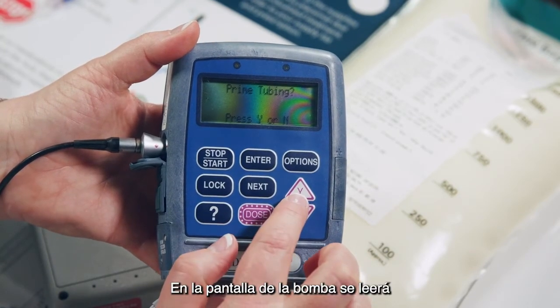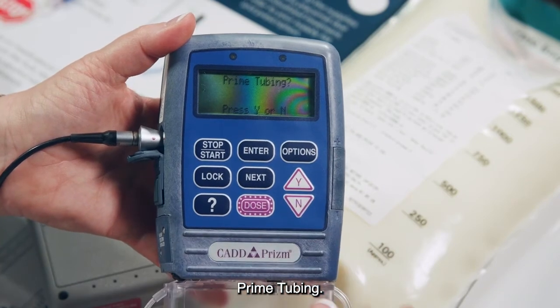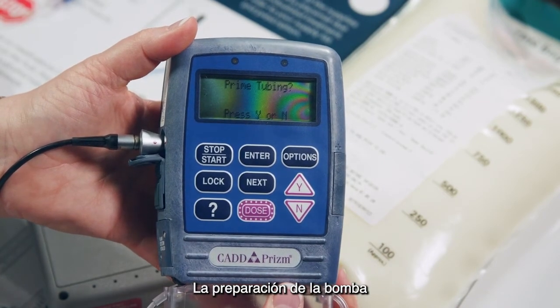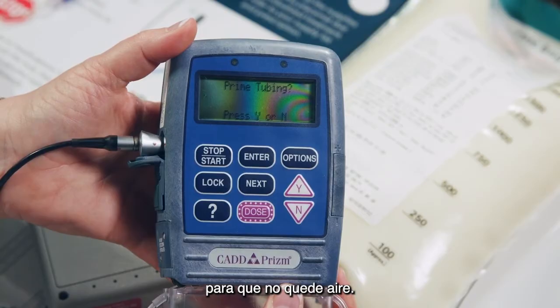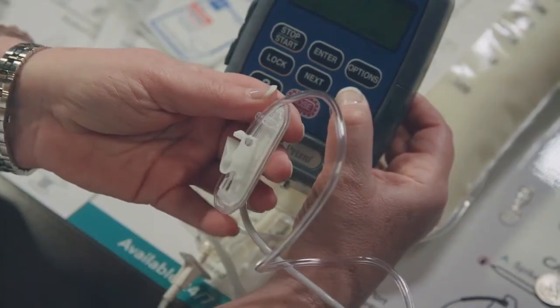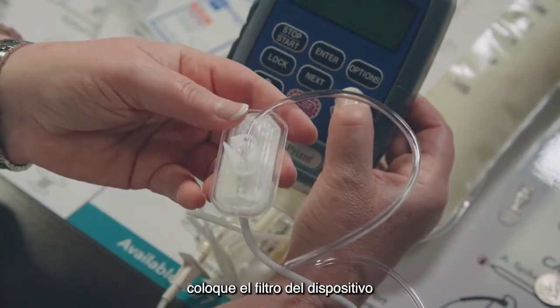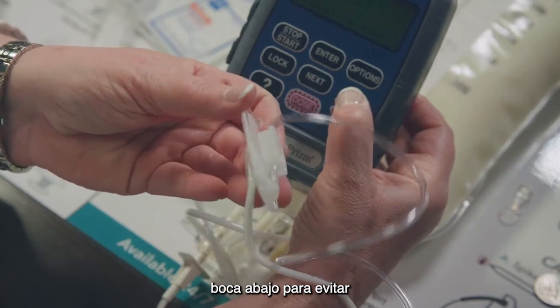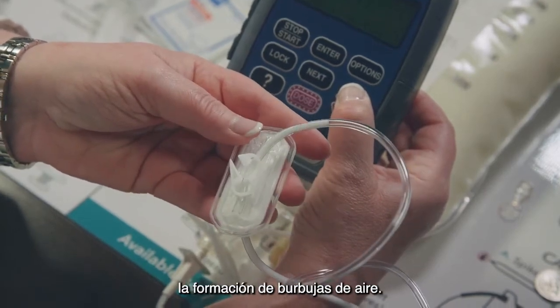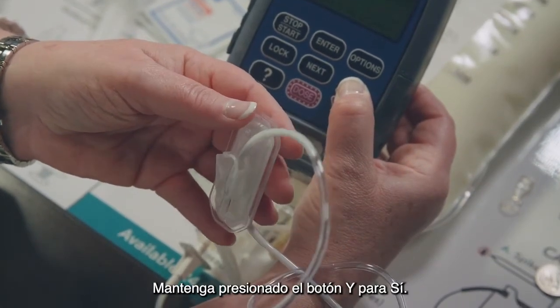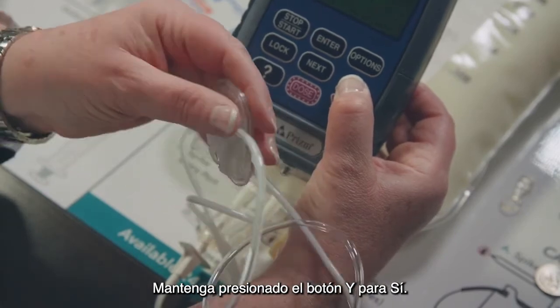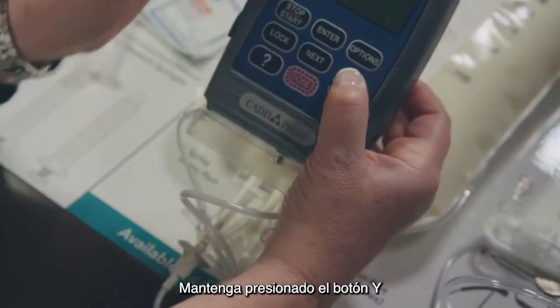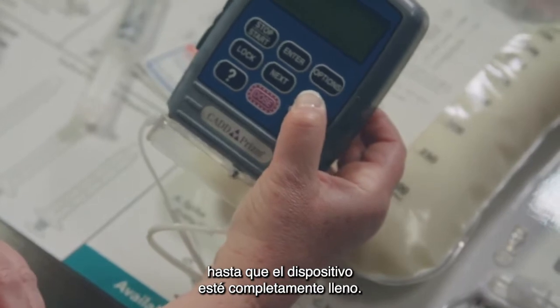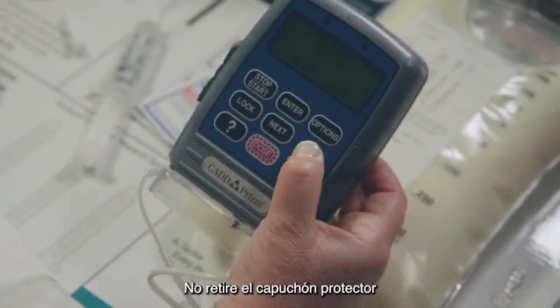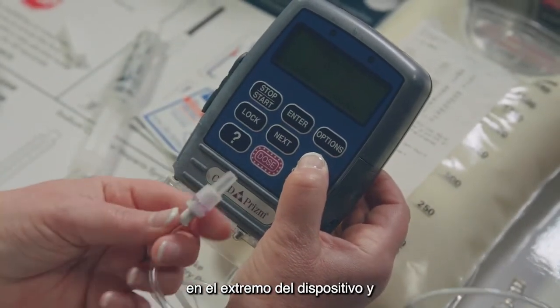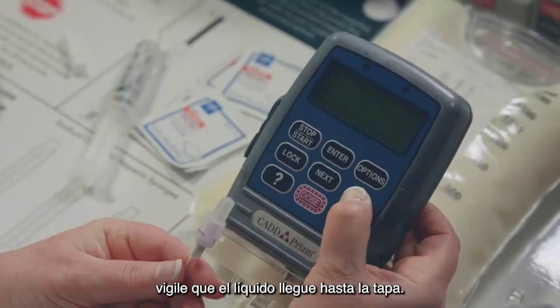The pump display will then read Prime Tubing. Priming will push fluid through the tubing so there is no air left in the tubing. During priming, the tubing filter is to be held upside down to prevent air bubbles in your tubing. Press and hold the Y for yes. Hold the Y button down until the tubing is fully primed. Do not remove the protective cap on the end of the tubing, but watch for fluid to fill the cap.